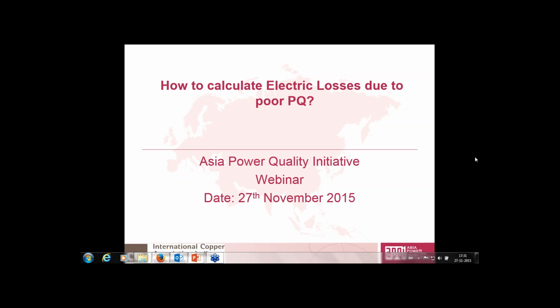I just had something to add on that last point. I am aware that some utilities in India are now using IEEE 519 as the basis for harmonic reporting. So if you're a facility that's connecting to the grid, some utilities are saying that you have to be within the limits of the IEEE 519. Yeah, that is reflected in the IEGC, the Indian Electricity Grid Code.